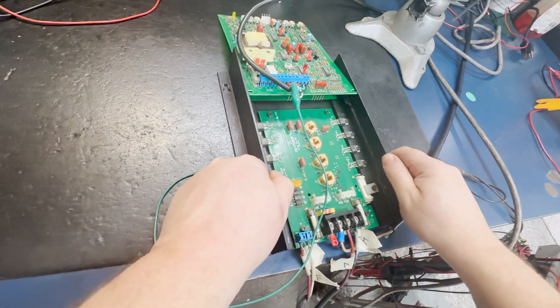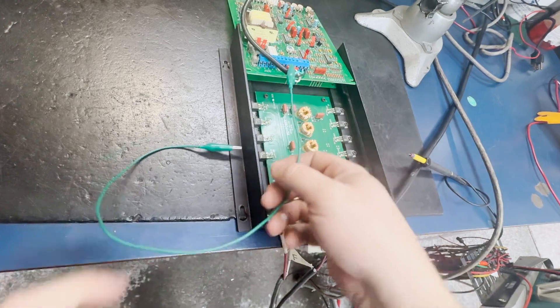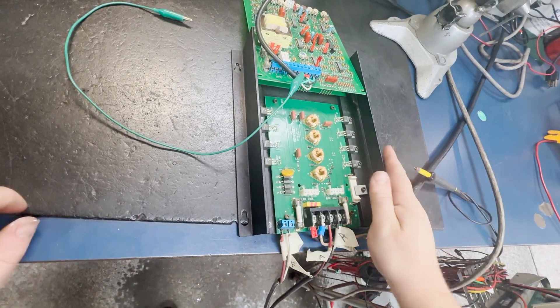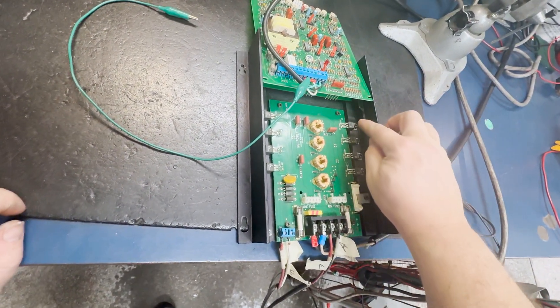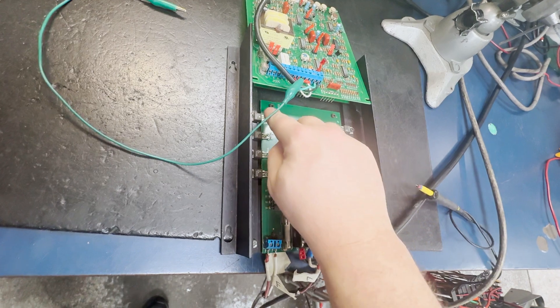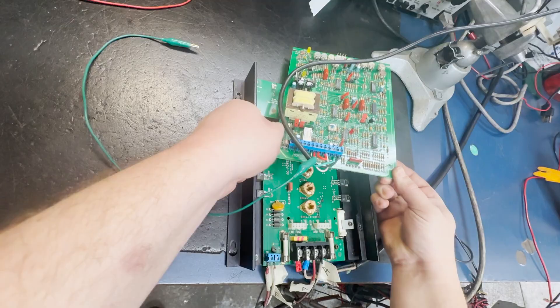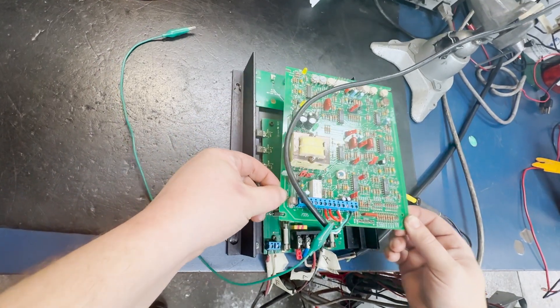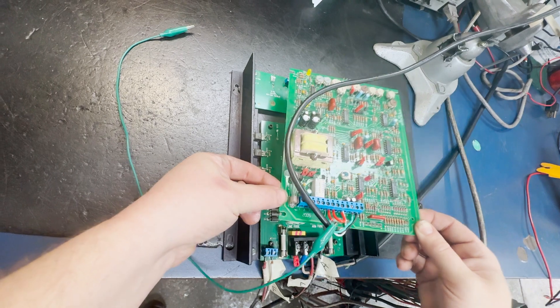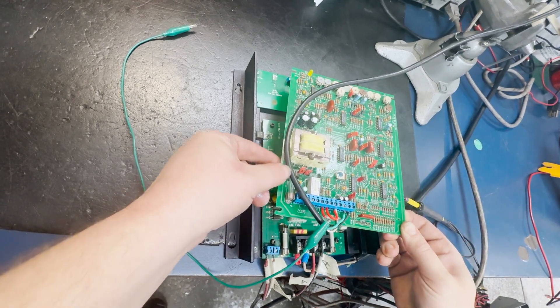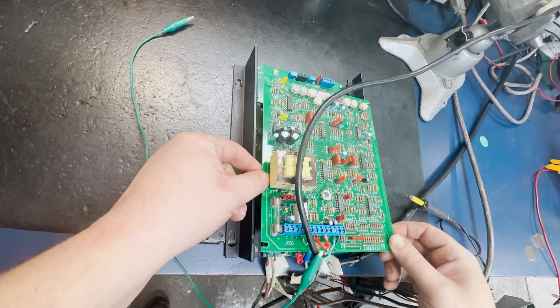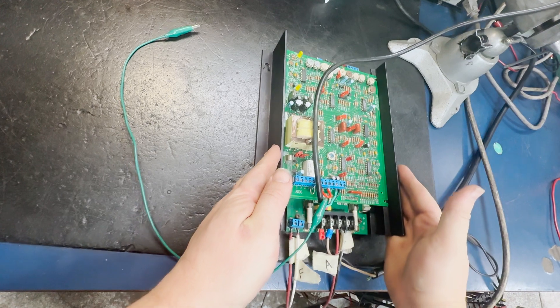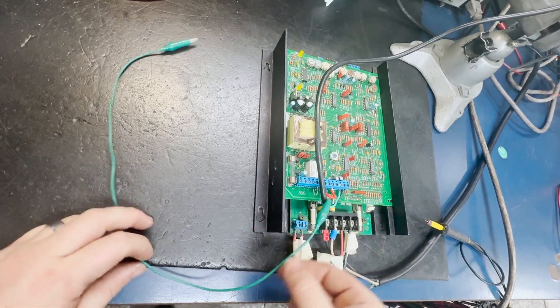We have already replaced all the SCRs that were blown on the output of this drive. We have also replaced all of the capacitors on the logic board, so that we know that this drive will last a long time in service. We will re-establish the connections and go ahead and run our test.